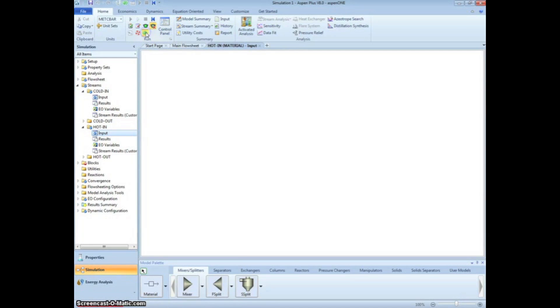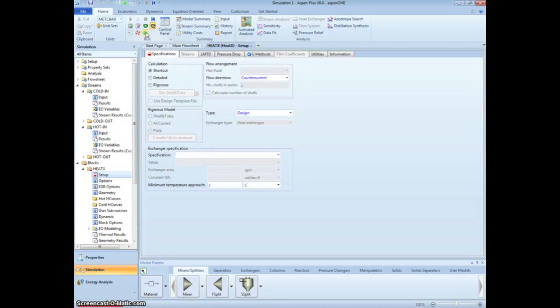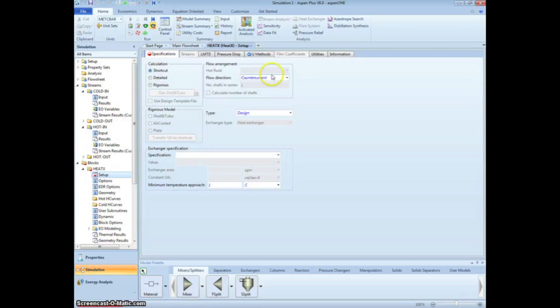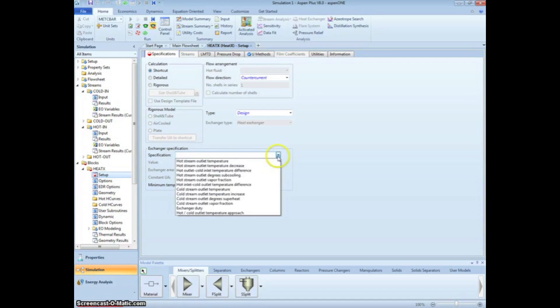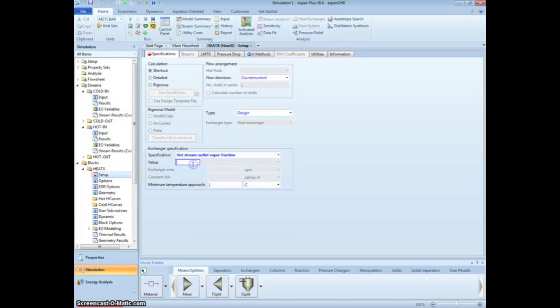Click the Next arrow to specify information about the heat exchanger. We are going to use the shortcut method so we do not need to know the exact geometry of our exchanger. We will keep the flow as counter current and use the design method. From the problem statement, we are told the hot stream outlet vapor fraction is equal to 0. We can specify that on this screen.